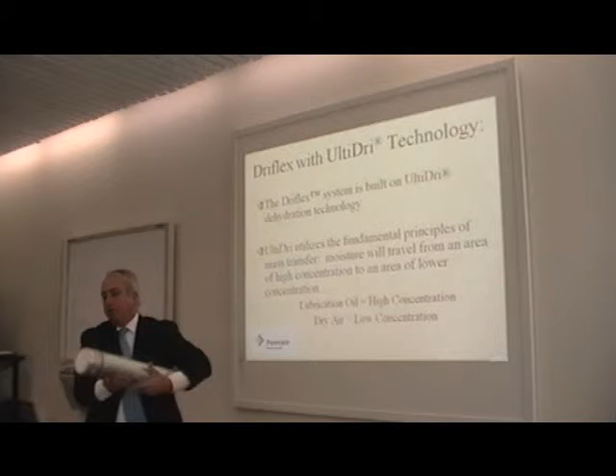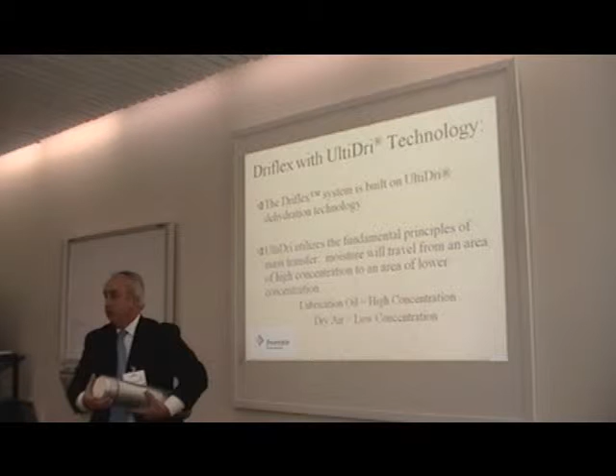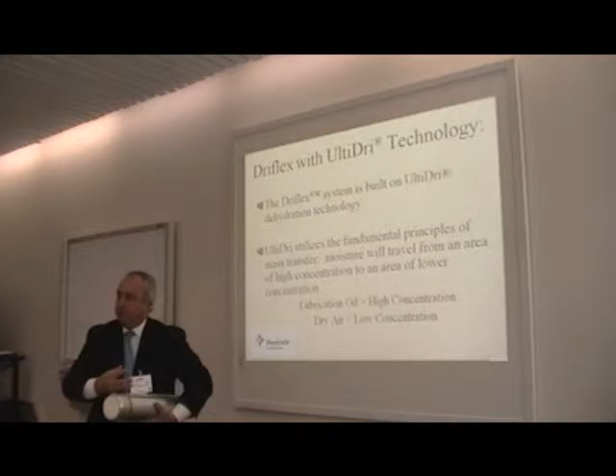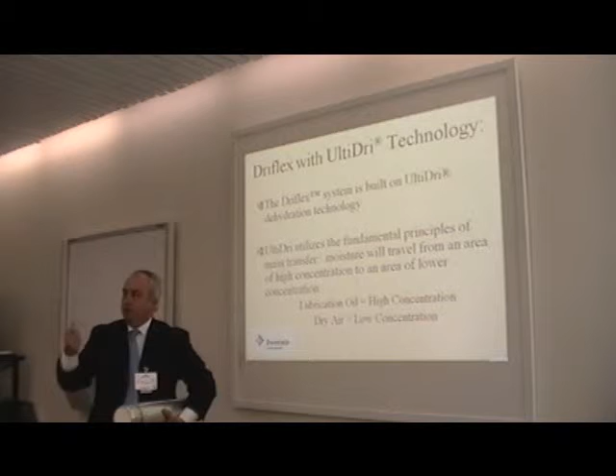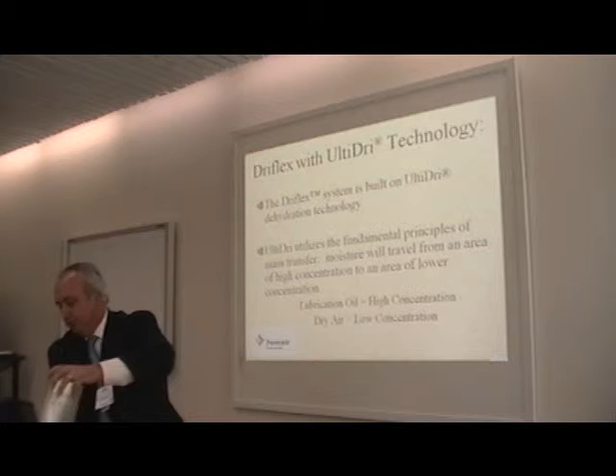In this case, you have a moisture exchanger - this is the internals of one unit. The oil flows down the inside of this tube bundle, we'll send this around in a second. There are about 6,000 individual tubes in here, so it's like a heat exchanger in miniature. You've got oil flowing down the inside of all these tubes, and you then have dry air on the outside. We can actually extract the moisture from the oil through the membrane surface and into the air. So essentially we exchange - the mass transfer direction is moisture out of the oil into the air and exhausted away.